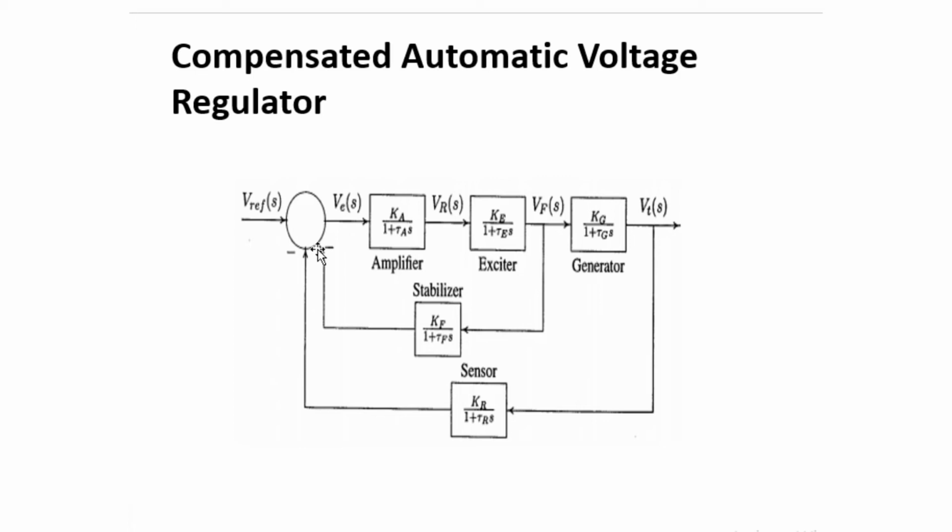So the power system stabilizer or excitation system stabilizer will damp the oscillation by regulating the generator field voltage, and it will result in a swing of the VAR output. So the gain of the power system stabilizer is chosen very carefully, so that the resultant gain margin of the volt to VAR swing should be acceptable. You can see here the transfer function of a stabilizer. It is a function of a gain Kf and the time constant Tf.